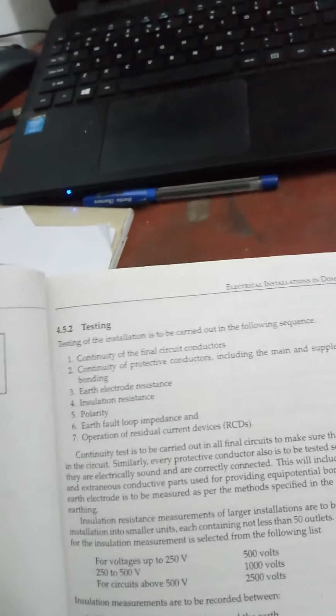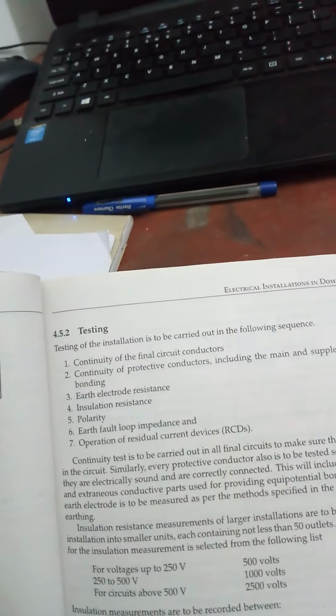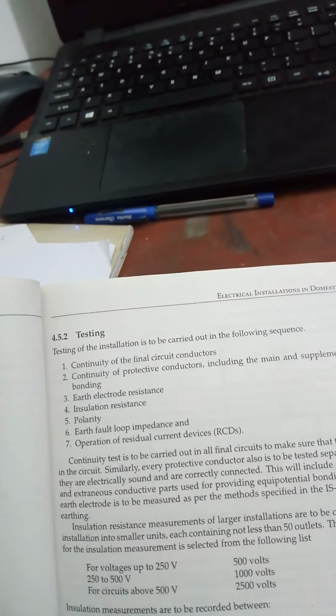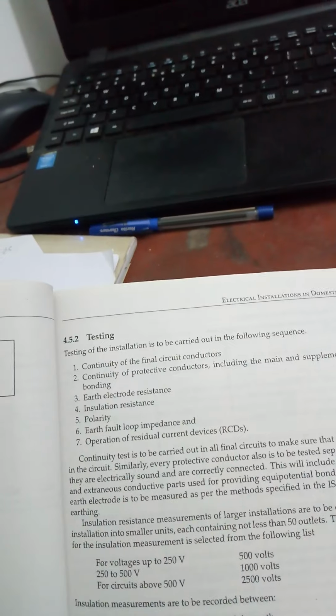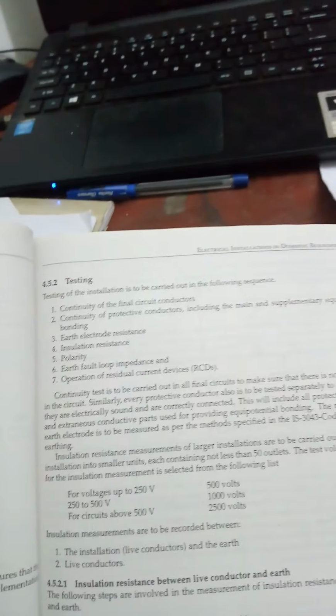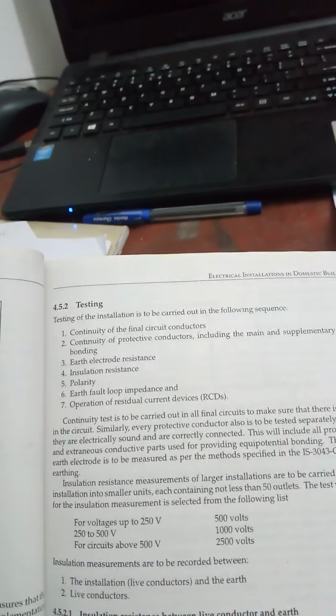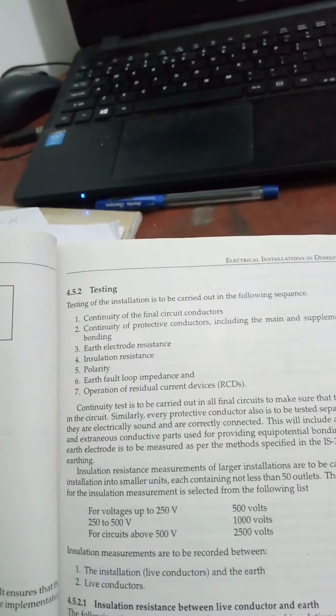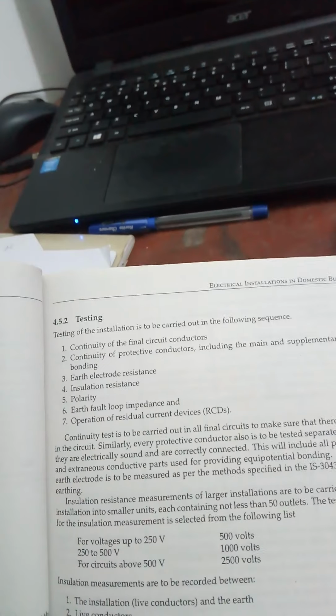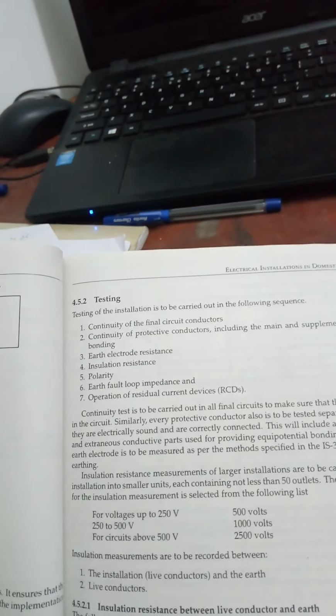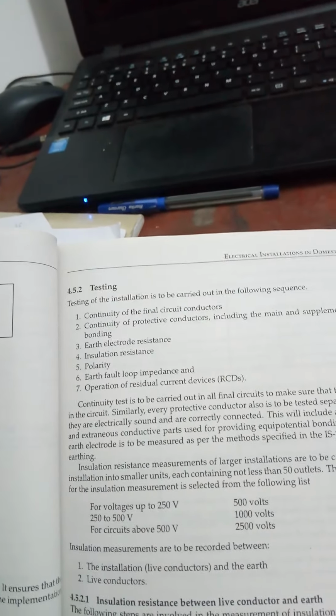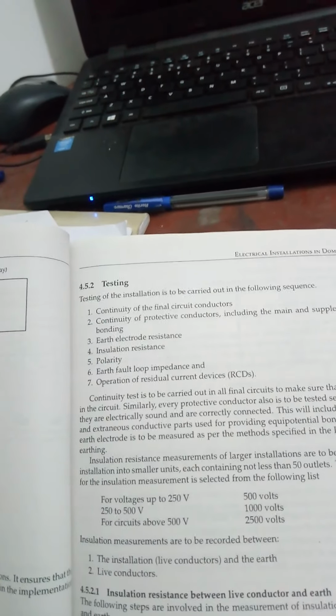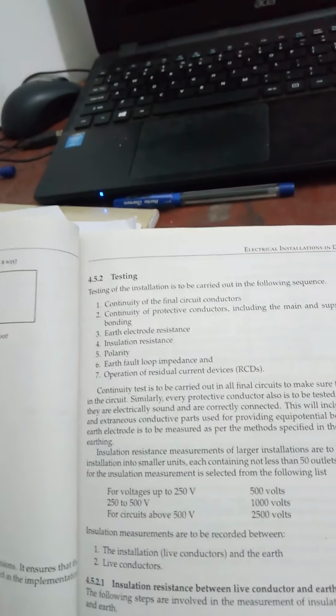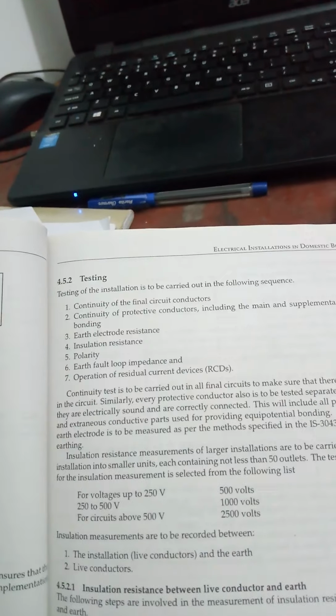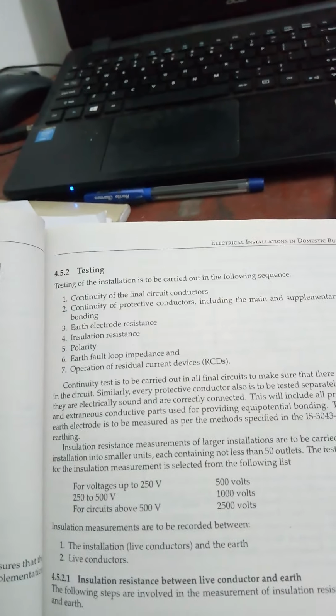Testing of installation is usually done by various methods. Continuity test of the final circuit conductor. Continuity test is carried out in all final circuits to make sure that there is no discontinuity of supply. Also, continuity of protective conductors, including main and supplementary equipment, is done to make sure that electricity can easily flow through the circuit, or it is electrically sound and correctly connected. This will include all protective conductors and other conductive parts used for providing equipotential bonding.